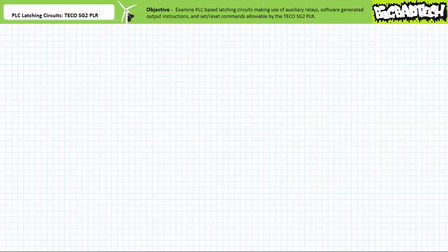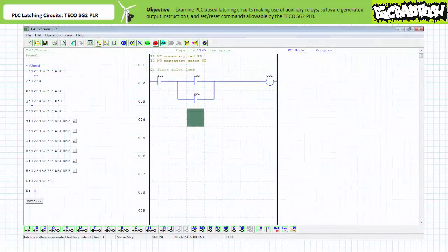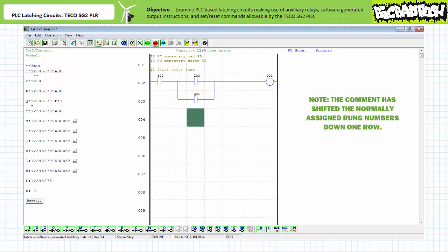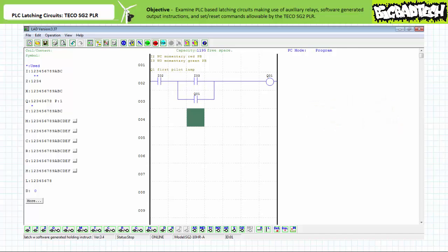Let's now examine holding circuits made possible through the use of software-generated output instructions. Using the TECO SG2 client programming software, we can create a holding circuit by incorporating a software-generated make instruction examining output Q1 on rung 2. This yields almost identical behavior as previously, however this program uses less rungs and proportionally less memory. Rung 1 is a series configuration of a make instruction examining input I2 and a make instruction examining input I3 controlling output Q1. Rung 2 is a make instruction examining output Q1 in parallel with the make instruction examining input I3 in rung 1 — the software-generated holding contact, directly mimicking the function of an auxiliary contact in an electromechanical circuit. Using this more streamlined approach, the program is ever so slightly smaller.